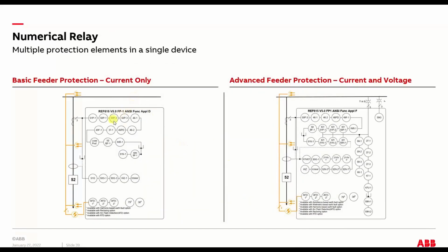And then here, just real quick, these are examples of modern, current day relays, and the circles in them just give you a feeling of the number of protected devices you can get all in one box. This is a really basic numerical relay, and you've got your 50-51, all three phases, plus you have ground current, neutral. This AFD is for additional functions for arc flash detection. So you have basically all these devices built into one box.